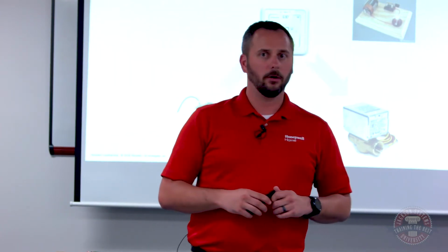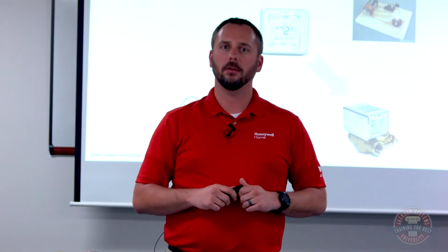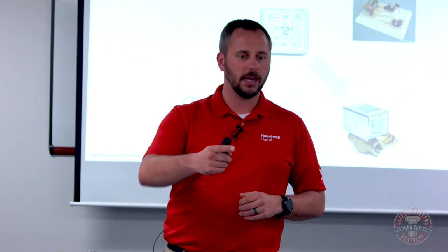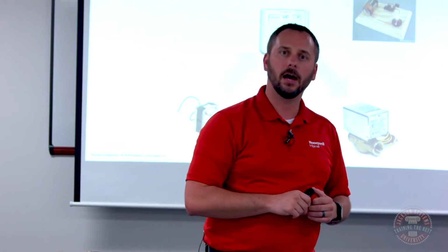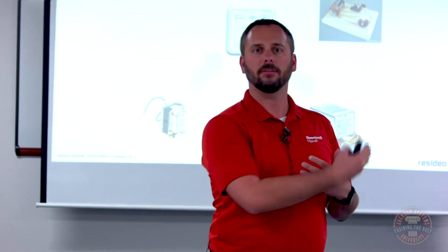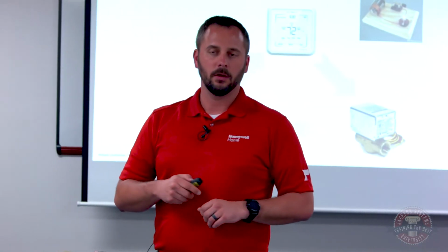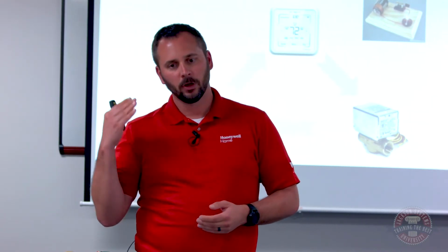So we've got the transformer, taking our 120 volts and converting it to 24, and we're throwing it up to the thermostat. Once that thermostat gets a call for heat, it basically throws the power out to the zone valve. The zone valve then gets the power, and you have to complete the circuit and it goes back. As you're learning, if you're not real proficient in electrical circuits, one thing I will advise, because it'll help you a lot as you get into more advanced circuitry: always start from the power supply, go out and come back. Don't ever work backwards, because as you get into more complex controls, it will start to get very confusing. So you always start from the power supply and move out and come back.